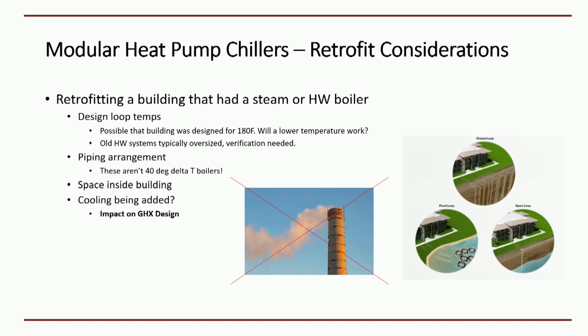Same thing with piping arrangements. You might be dealing with an existing hot water system. Maybe it was designed around a 40 degree delta T. Your pipes might be a little smaller than what you need. That's going to lead us right into pumping strategies and how we might achieve and make that building successful. But these are things you definitely have to pay attention to, because again, these aren't instantaneous hot water heaters. They're not boilers that really like these wide ranges of design. We just want to work within that to really make the system efficient and first cost friendly.